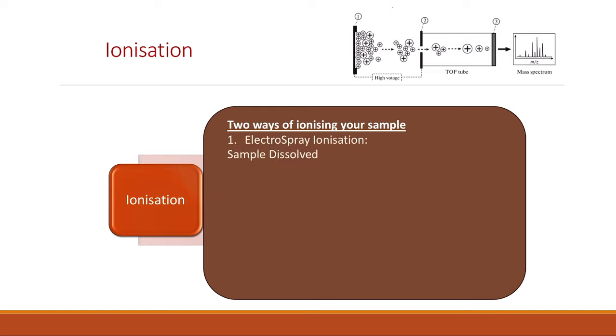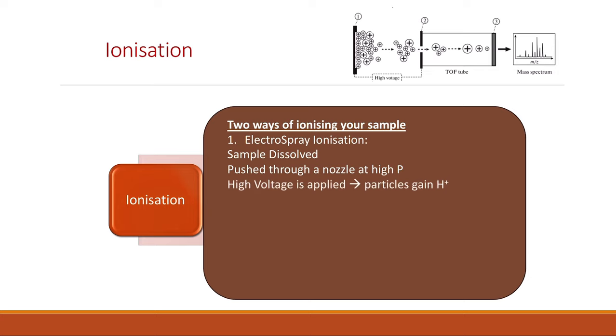There are two ways of ionizing your sample. The first is called electrospray ionization. In electrospray ionization, the sample is dissolved first, then it passes through a nozzle at high pressure, and a high voltage is applied. When the high voltage is applied, the particles gain a hydrogen ion, which means the sample turns into a gas made of positive ions.